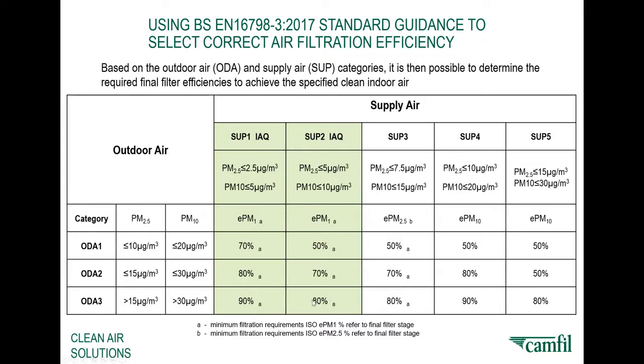You need an 80% efficient filter, and that would be an EPM1. In other words, an 80% efficient filter at removing PM1 particles. That's particles 1 micron and below. So that just gives you a quick flavour of the classifications there.